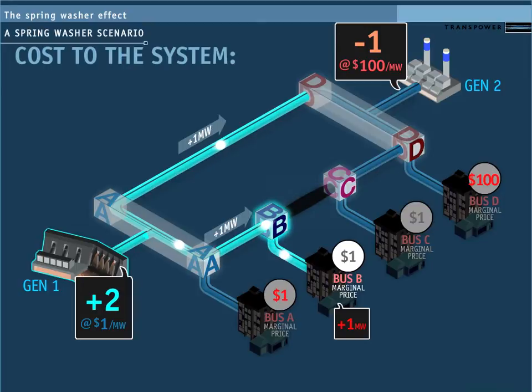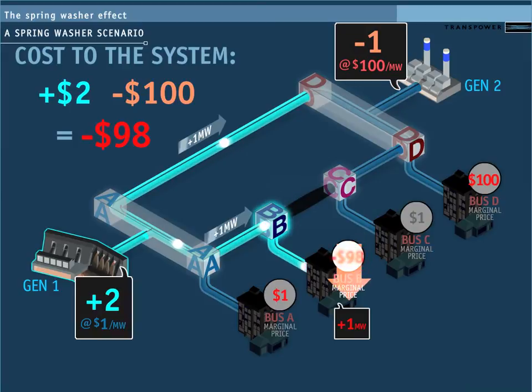So now we can calculate the cost of supplying the next megawatt of load to bus B. It would require 2 megawatts from generator 1 at $1, and it would require generator 2 to back off by 1 megawatt for negative $100. So the final marginal price at bus B would be negative $98.